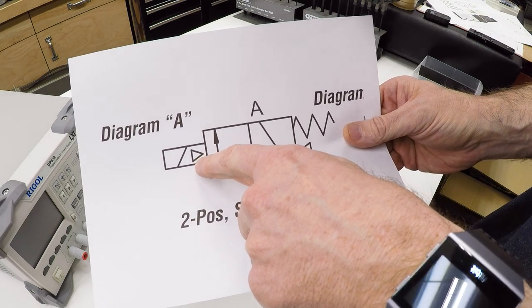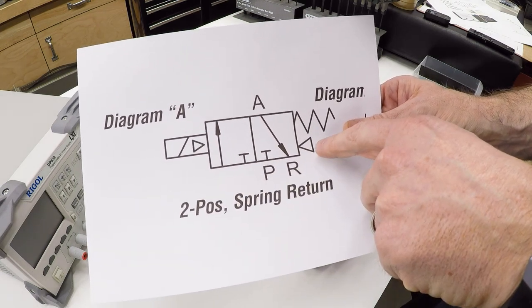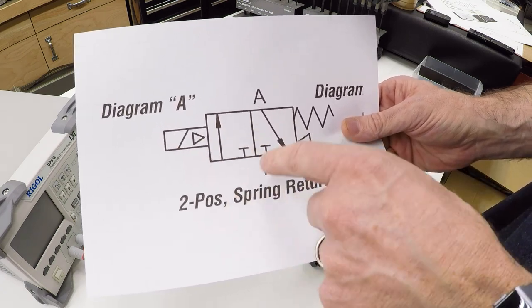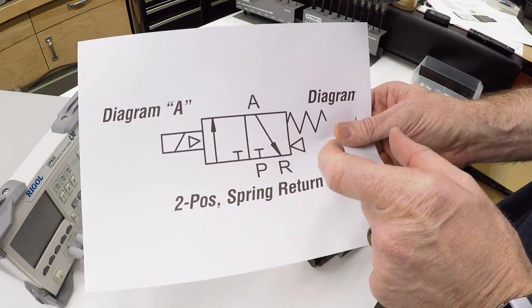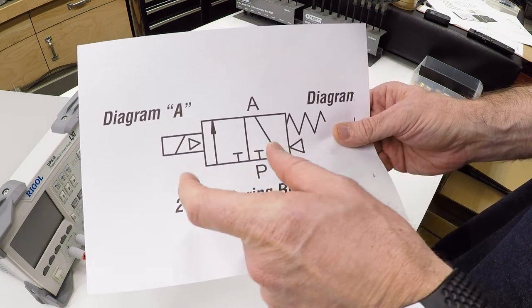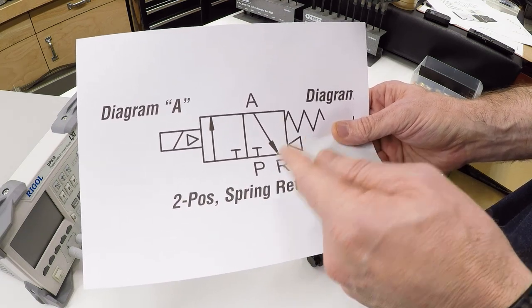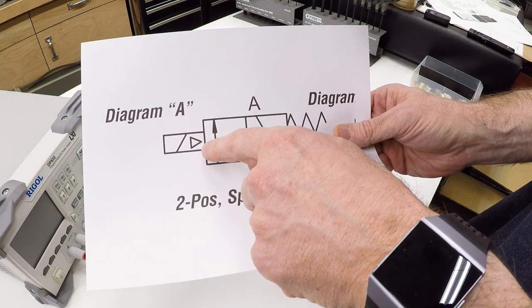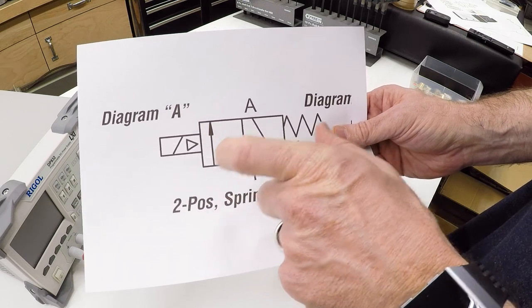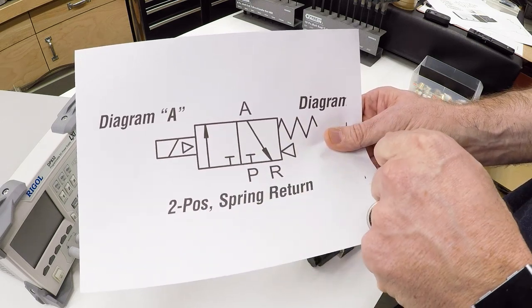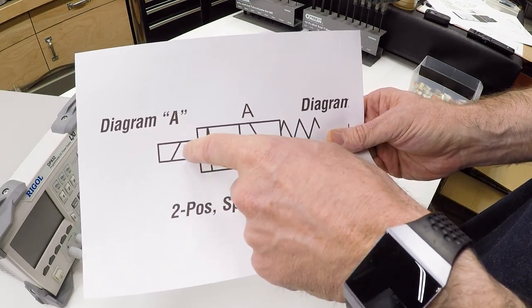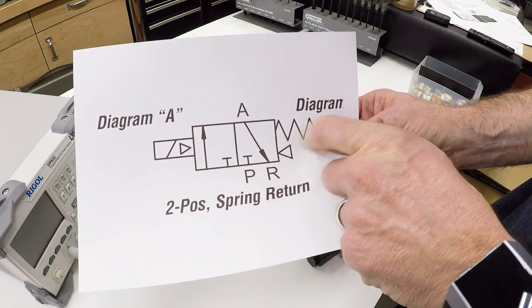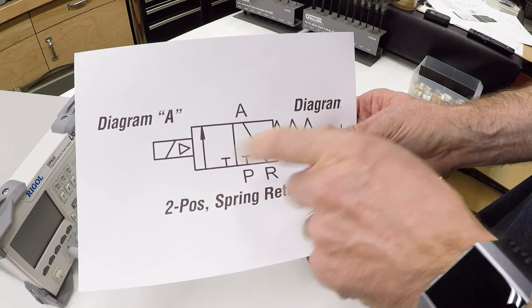One other thing on these diagrams, you'll see these little arrows here. Those indicate that it's a pilot valve. What that means is that the electromagnet is not providing all of the force to throw the shuttle in the valve back and forth. It's also using air pressure to help. So the solenoid is actually just opening up a small valve that then allows air pressure to throw the large valve to the opposite position.